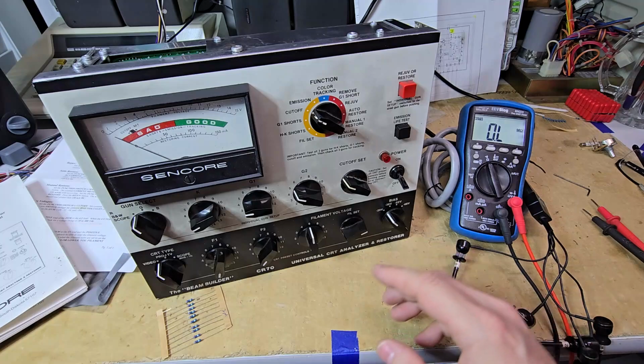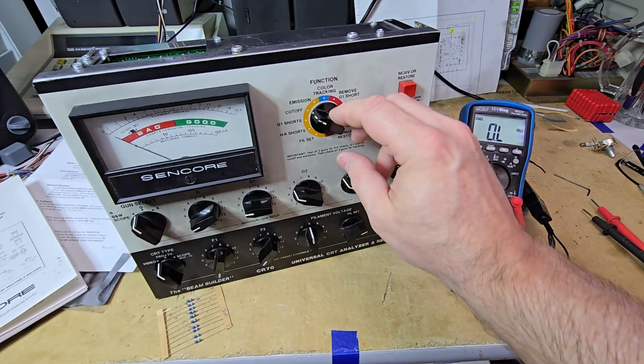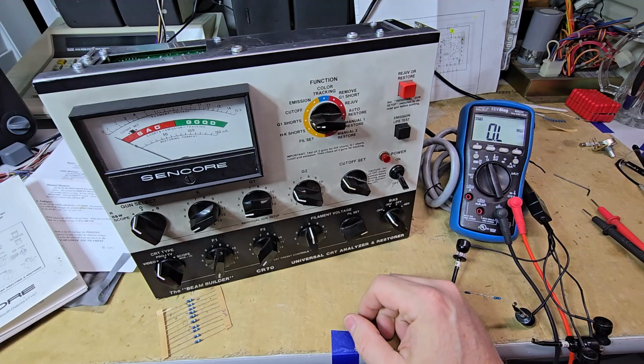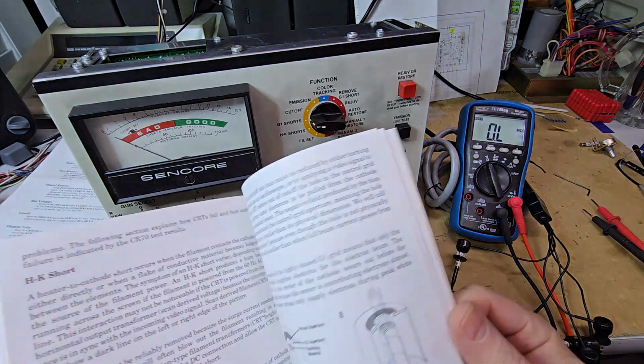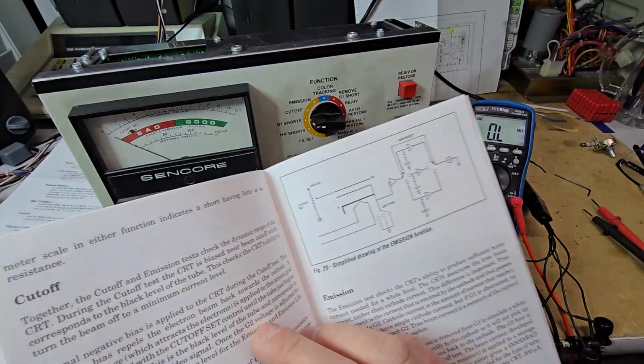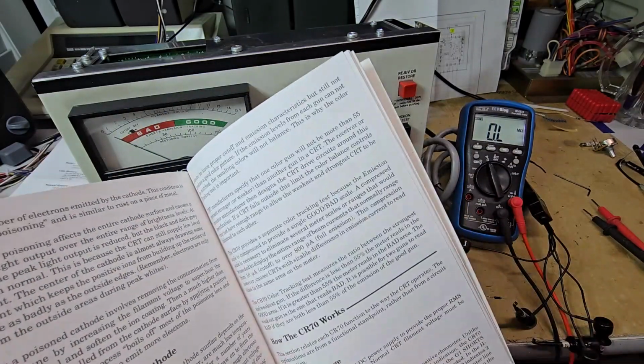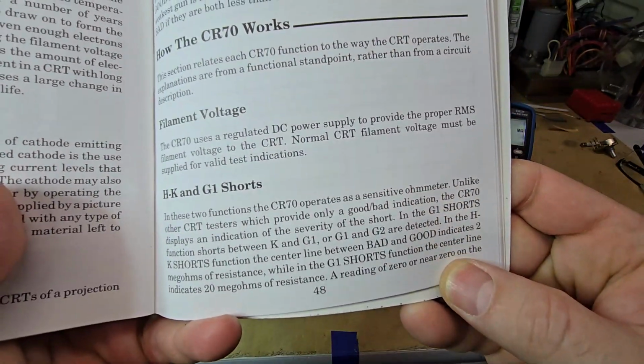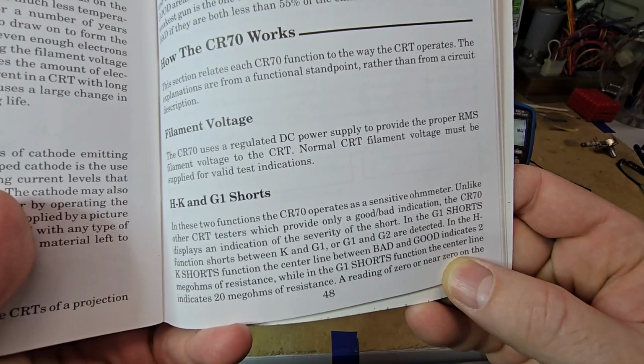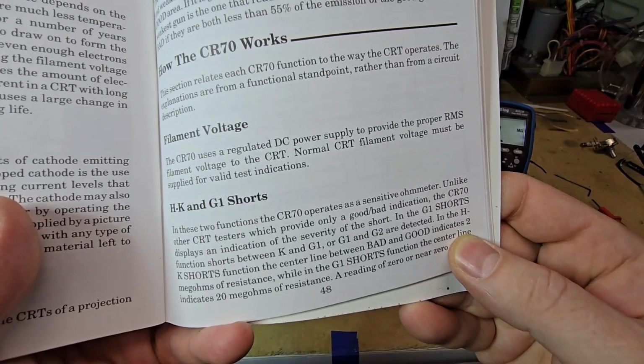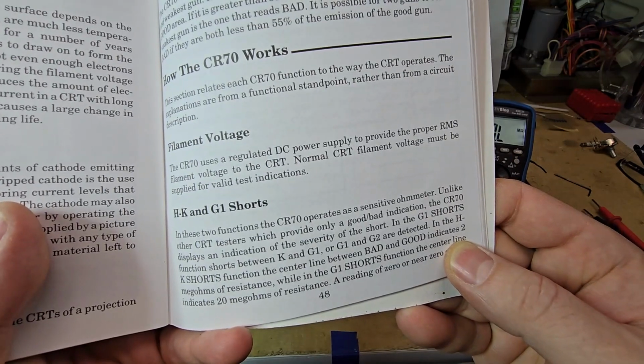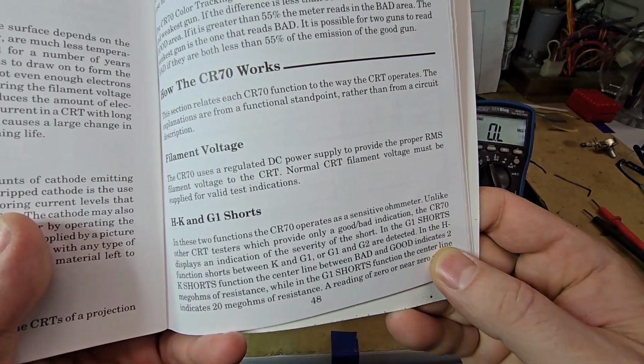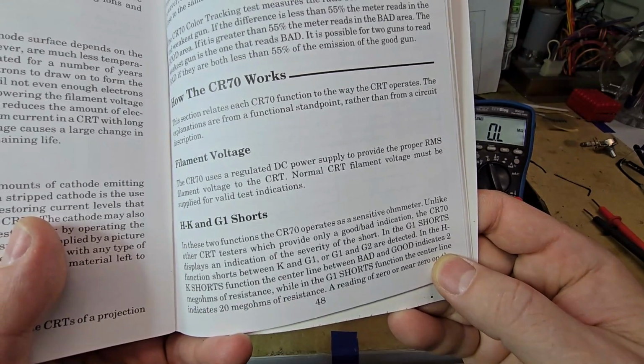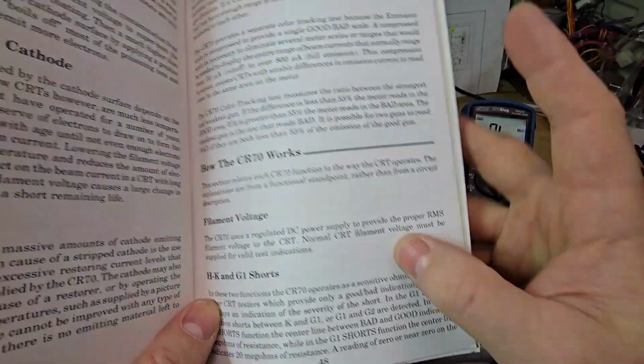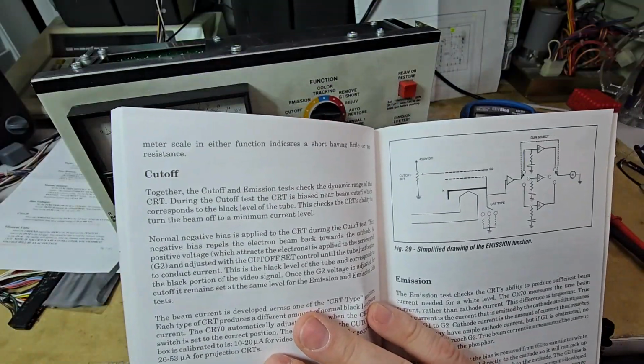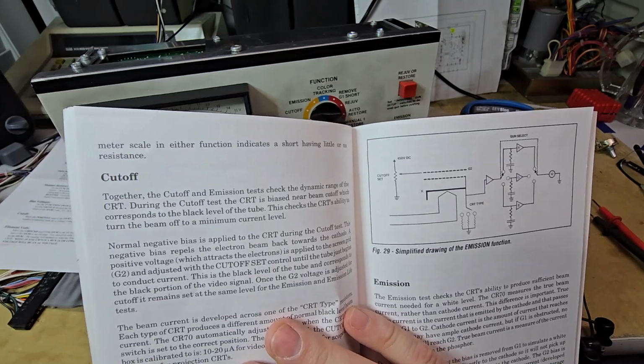And then we're going to go to our G1 short test. And further in the book, let's see if there's a shorts. Let's see here. It says in HK shorts function, the center line between bad and good indicates 2 mega ohms of resistance, while G1 shorts function center line indicates 20 mega ohms. A reading of near zero on the meter scale in either function indicates a short having little or no resistance.